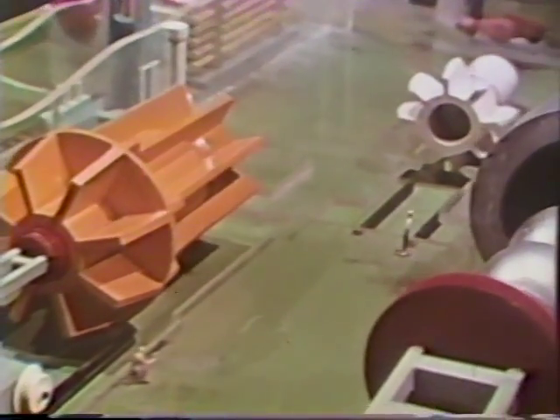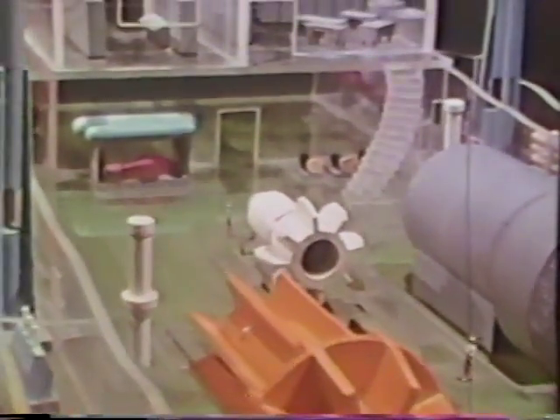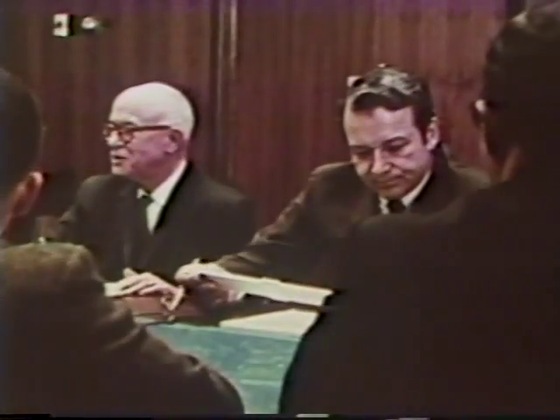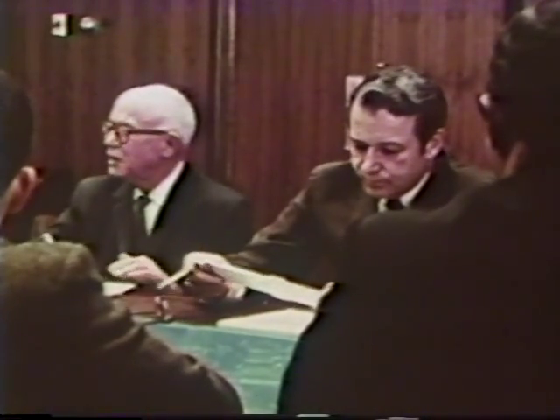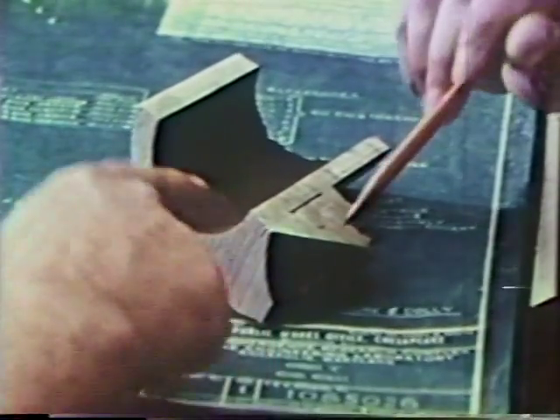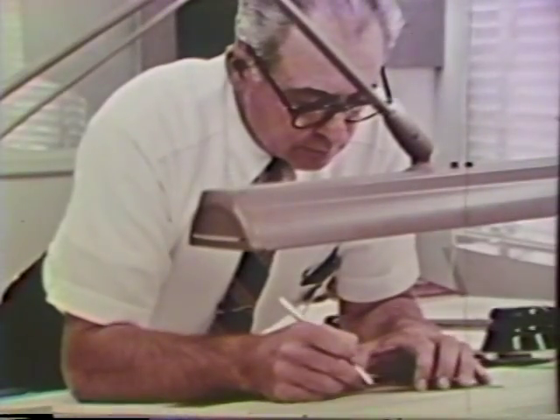The concept of a deep ocean pressure testing laboratory had already been formulated and a model built. There was space allocated for pressure tanks of various sizes, pumps, coolers, air compressors, transformers, and water storage tanks. The largest pressure tank envisioned would need a long test life at simulated deep ocean conditions — two million cycles at 9,000 feet, and capable of several thousand cycles at 26,000 feet. Gradually, plans emerged for constructing a mammoth testing chamber.